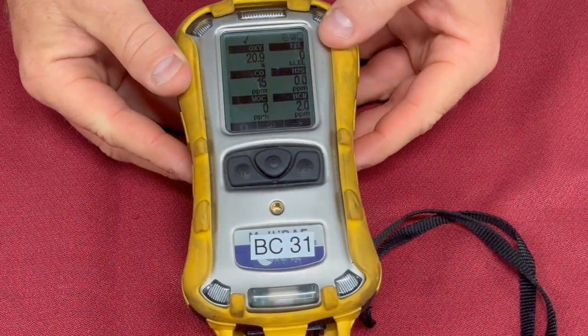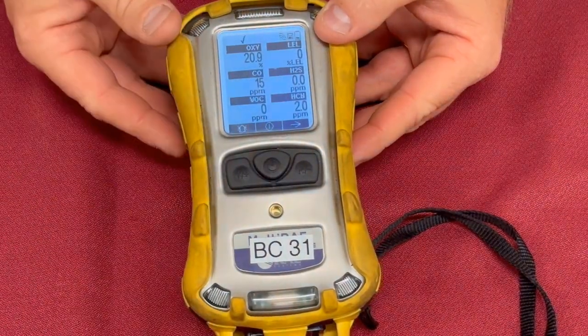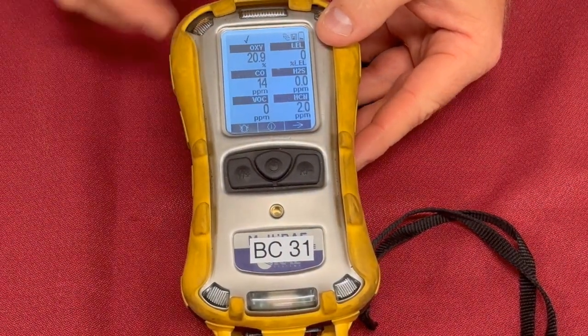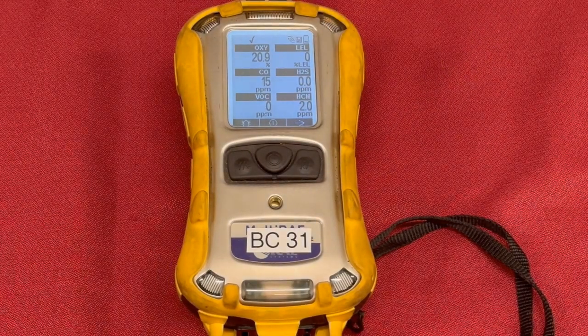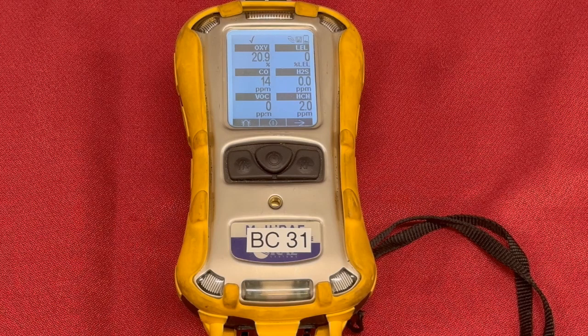So the next sensor we have, I'll turn the light back on, is the LEL, lower explosive limit sensor. This is a scale of 100. It's calibrated to methane, which is basically natural gas. The idea behind it is that's the most likely thing that you're going to come in contact with. It is designed to go into alarm at 10% of the lower explosive limit, 100% being the actual spot that becomes explosive.